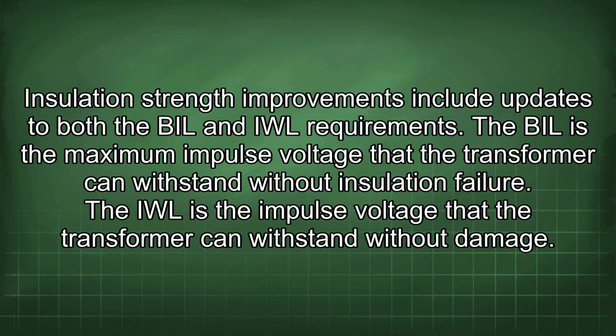Insulation strength improvements include updates to both the BIL and IWL requirements. The BIL is the maximum impulse voltage that the transformer can withstand without insulation failure.